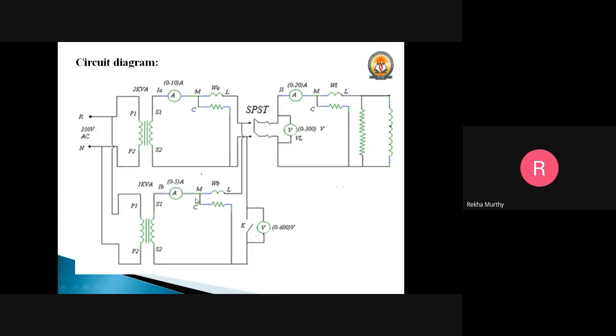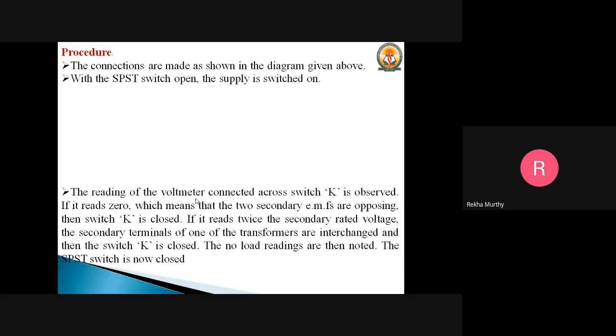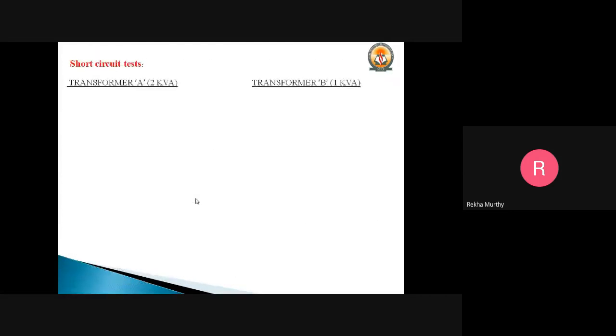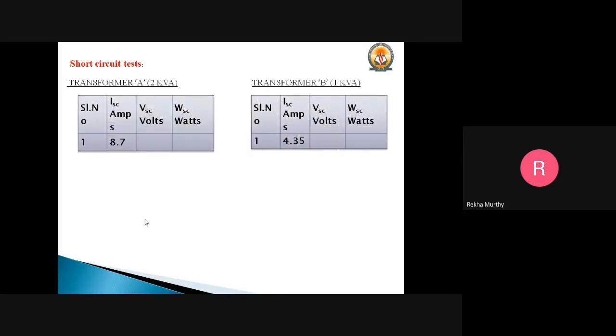Okay, fine. So what will be the readings which you are going to take from the short circuit test? One transformer will be of 2 kVA and another transformer will be 1 kVA. For the 2 kVA, the rated current is 8.7 amperes. So what will be the voltage? This is the same value which you will get as what we did in the OC and SC test in the first experiment. And we need to repeat to find out the VSC and WSC for the 1 kVA transformer. Obviously, it will be half of this value, so it is 4.35 amperes.